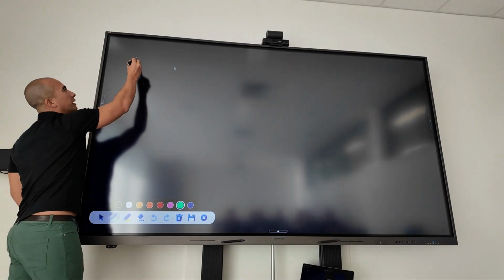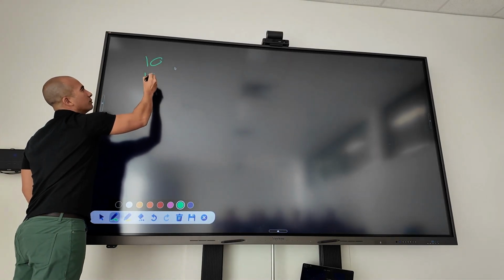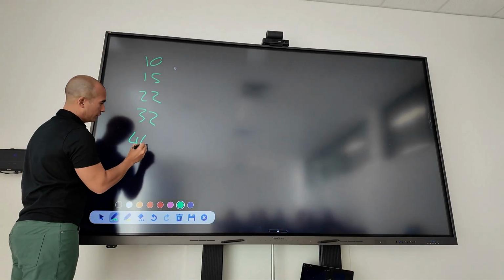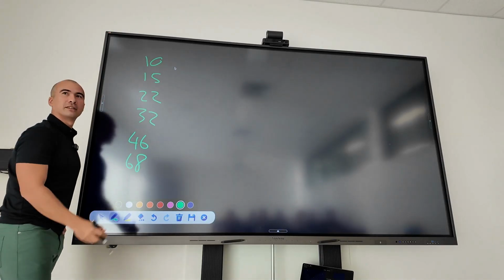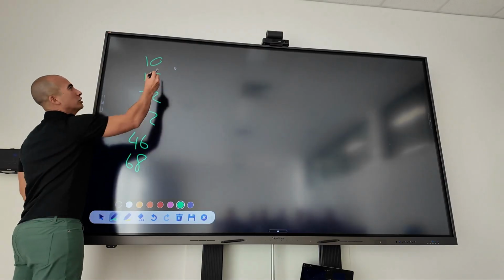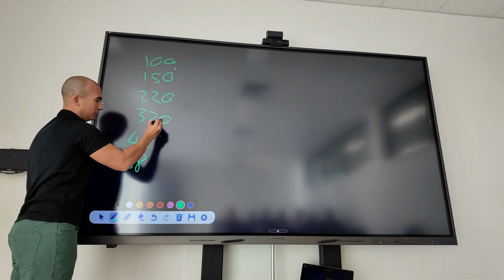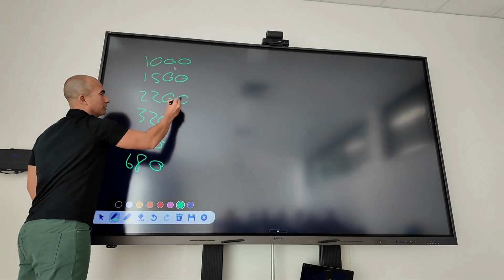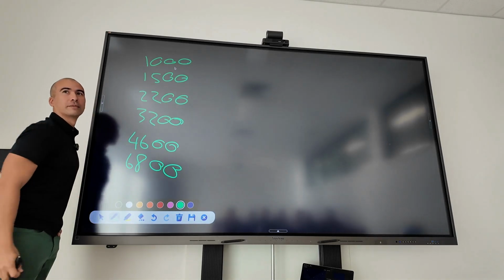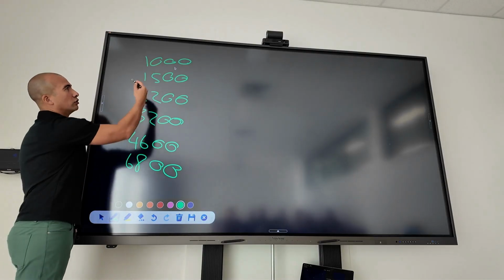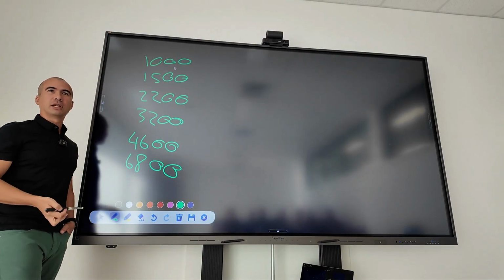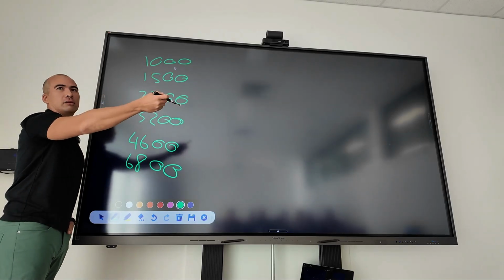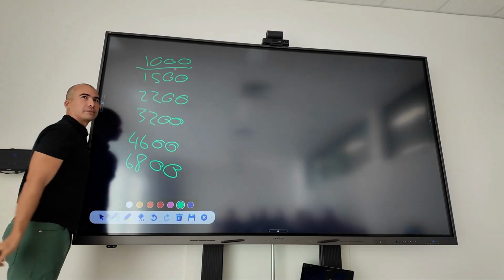The ISO viscosity grades go 10, 15, 22, 32, 46, 68, right? And then you just add a 0. Then you go again, add another 0. Yeah, and if you remember, each of these was plus or minus roughly 10%, right? So this one, if it was anywhere between 900 and 1100, it's considered an ISO 1000.